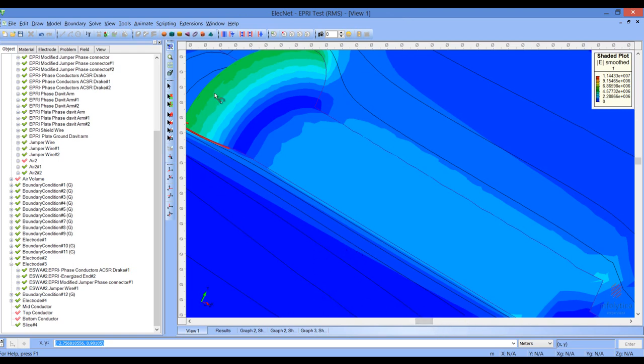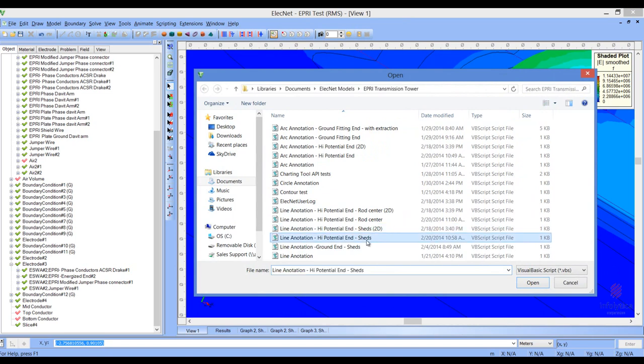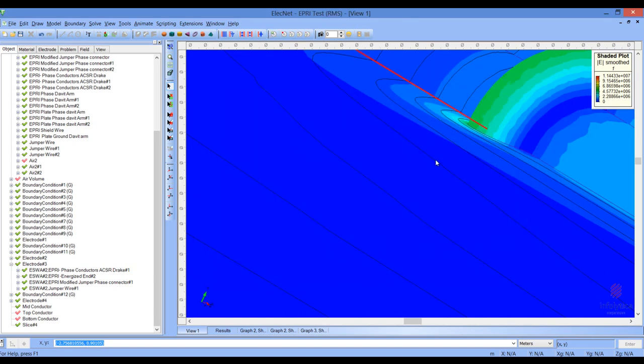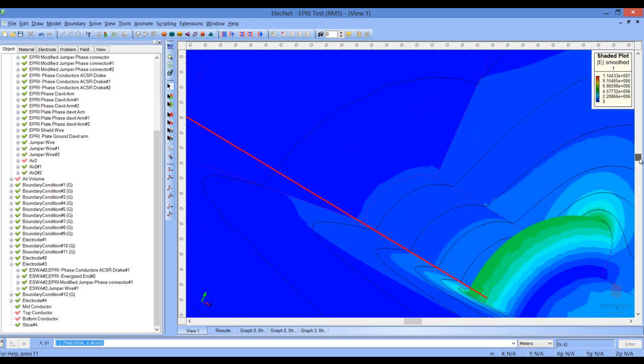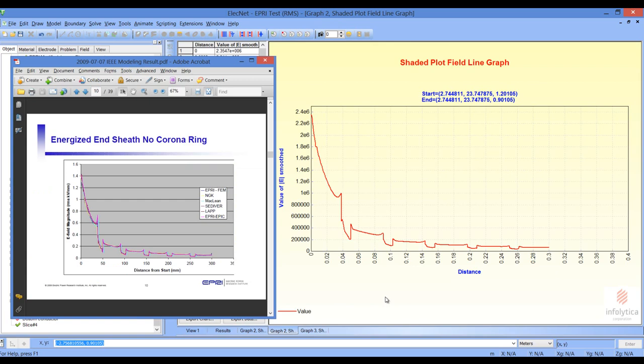Let's now look at the second contour. We'll bring up the contour along the sheath. You can see that it goes through at a distance from the sheath through the various sheds, and the result is shown in this chart. Again comparing to the EPRI document, we can see that on the energized end in particular, the field stress is a lot higher in the true 3D situation than it is for the 2D or single string structure.